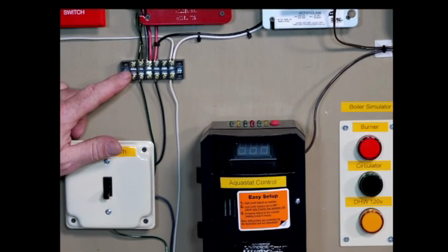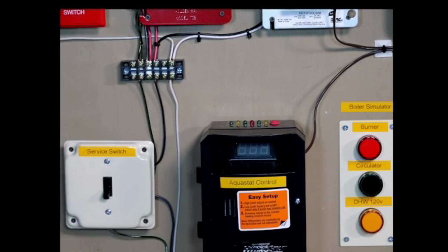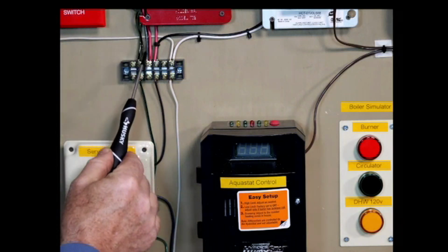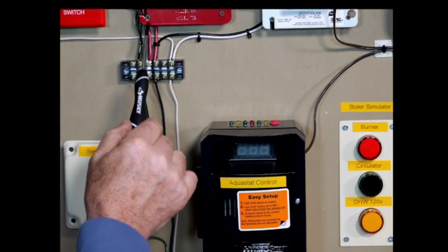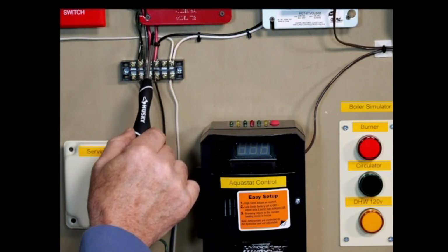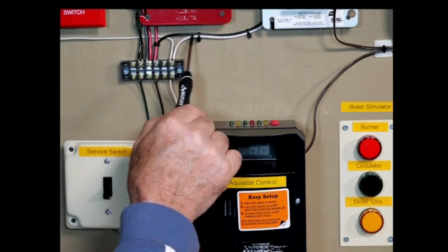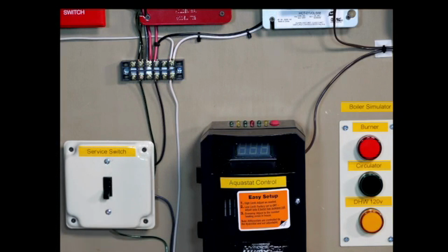We're taking a closer look at the connections that would be inside of the box for the thermal cutoff. I have them out here on a terminal strip to be able to see a little bit better what's going on and how this is connected. So as you can see here, the power comes from the emergency switch, drops down, and connects to the red wire, which is part of the thermal cutoff. So the power goes through the thermal cutoff and comes back down on this red wire, and that's connected to our transformer, and also dropping down to the service switch.